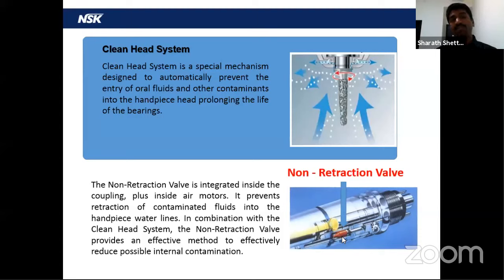Only having a handpiece with a clean head system is not sufficient. Such protection is needed whenever you use a non-retraction valve, and that is possible only when you have this non-retraction valve, which is available only on the coupling type of handpieces. So this is a very, very important aspect. Only when you have both these systems installed in your handpiece can you be 100% sure that cross-contamination will not take place from one patient to another.